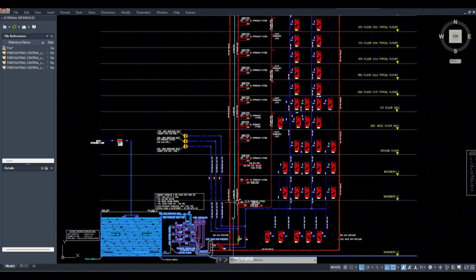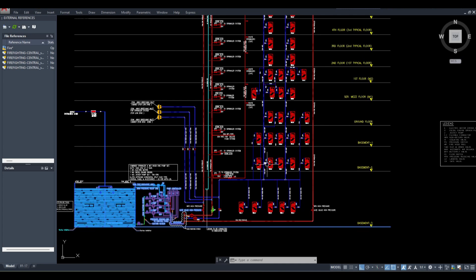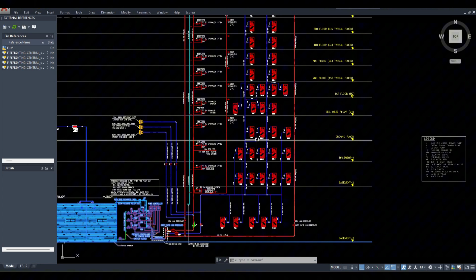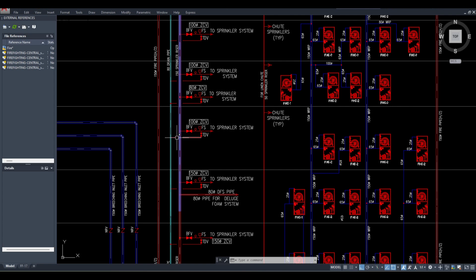So for example, for a hydrant system, I'll explain and it will become clear in the next session, but since you asked, let me explain quickly. When a fire happens at any floor, they consider that the fire hydrant of that floor will open, which should be within 6 meter proximity of your staircase, it should not be 6 meters away from the fire stair. Then they will consider that it has to operate along with the floor below it as well, and each hydrant has 250 GPM of flow. So if fire is on this floor, you consider the GPM of this floor plus the GPM of the floor below it.